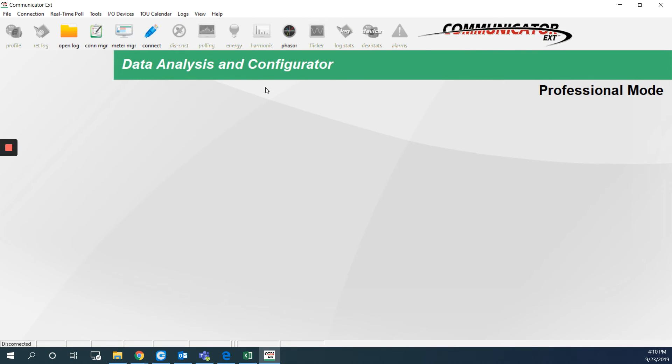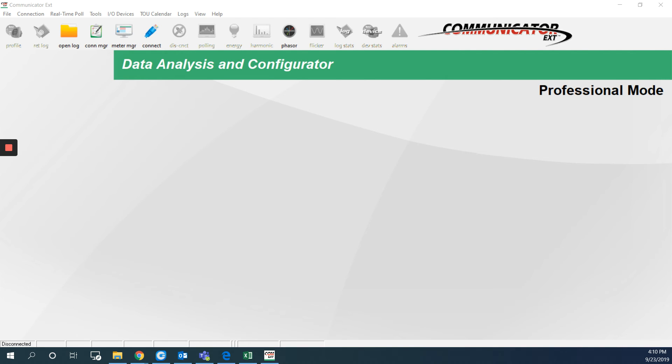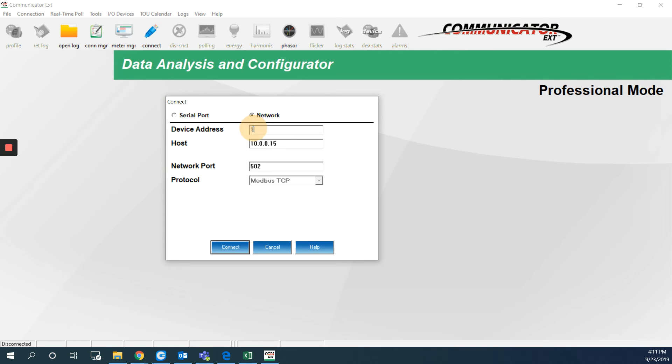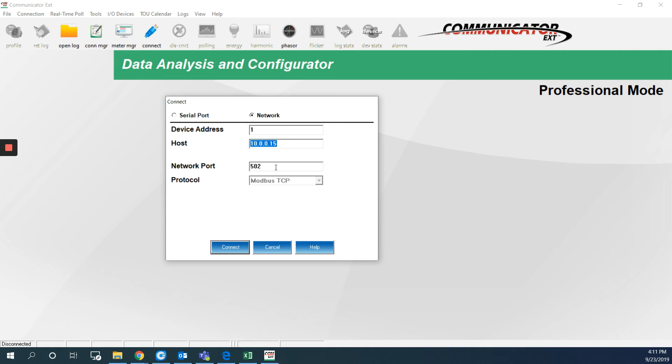I will connect to the meter using this icon here. And because I'm connected through the ethernet port, I will choose network here, not serial. The device address should be 1. And the host is the IP address for the meter, which is 10.0.0.15. The network port by default is 502 and the protocol is Modbus TCP because we are connected through the ethernet. I will hit connect.